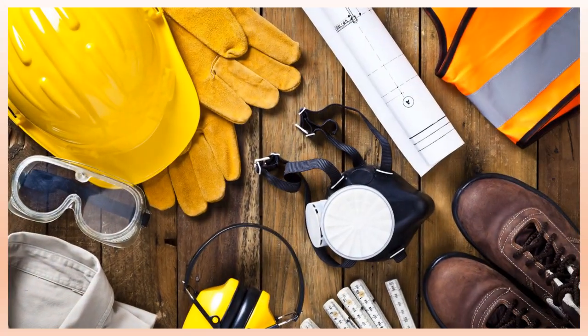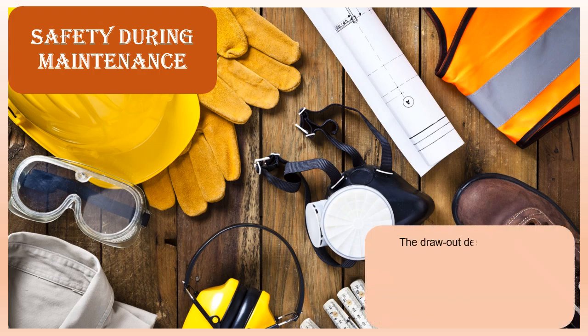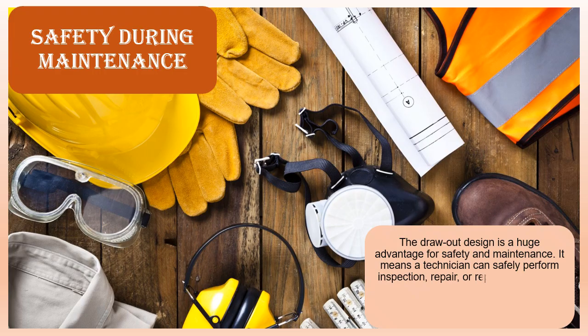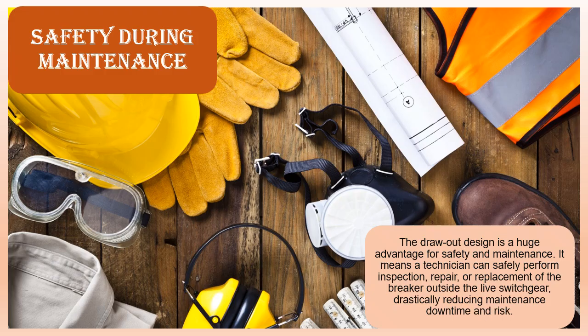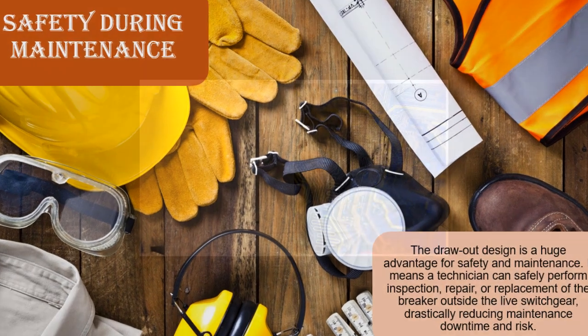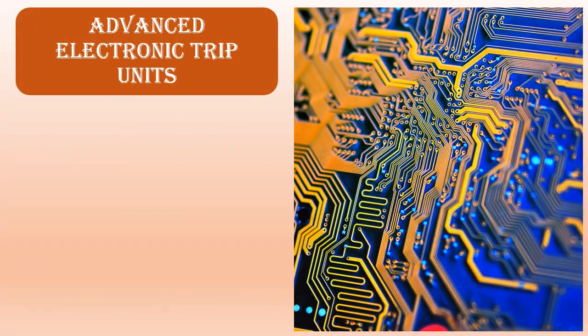Safety during maintenance. The draw-out design is a huge advantage for safety and maintenance. It means a technician can safely perform inspection, repair, or replacement of the breaker outside the live switchgear, drastically reducing maintenance downtime and risk.